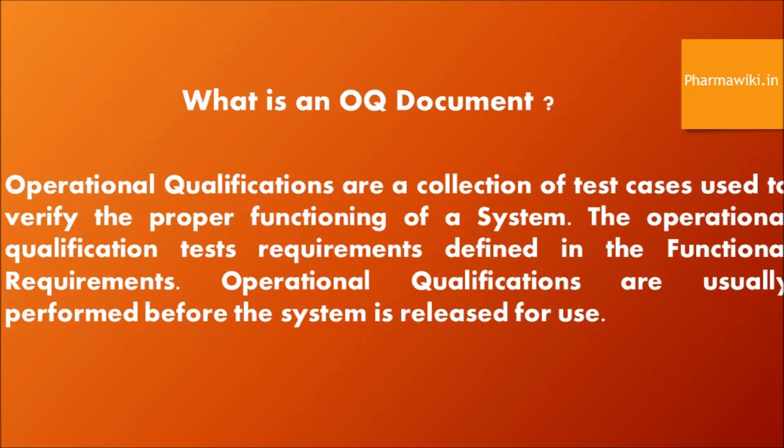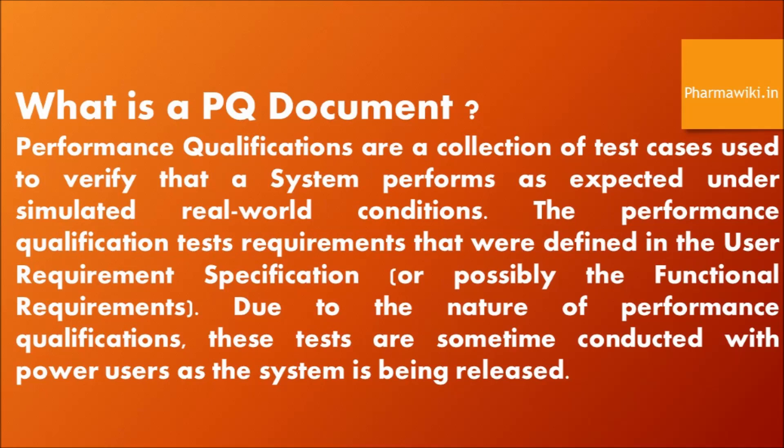Let us see what is a PQ document. A PQ document is a performance qualification. Performance qualifications are a collection of test cases used to verify that a system performs as expected under simulated real-world conditions. The performance qualification test requirements are defined in the user requirement specification or the functional requirements. Due to the nature of performance qualifications, these tests are sometimes conducted with power users as a system is being released.